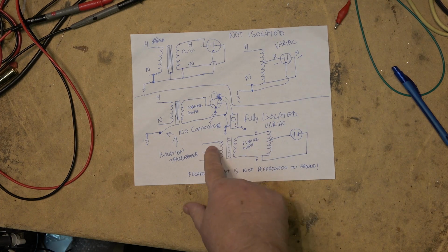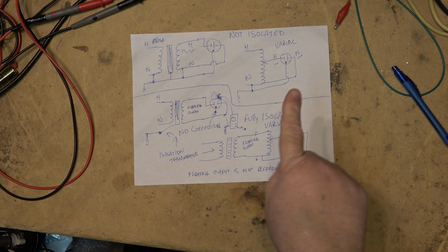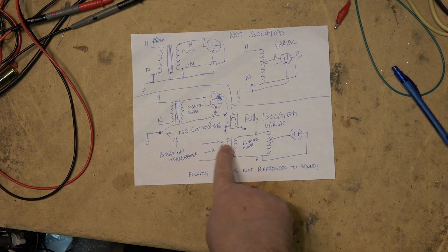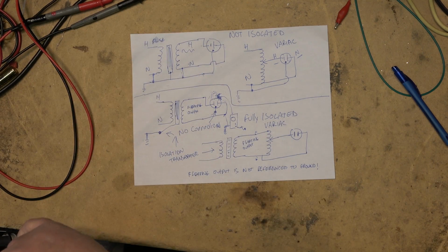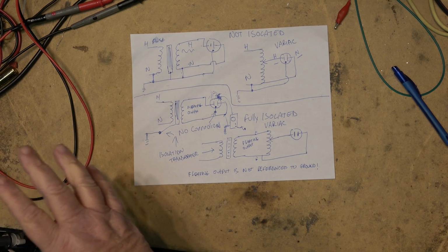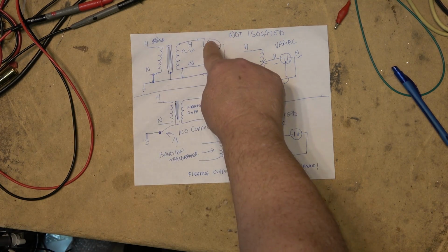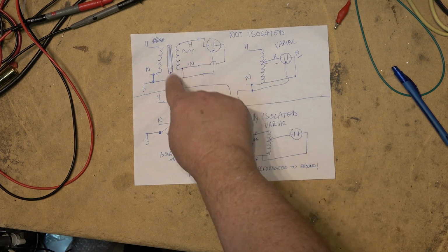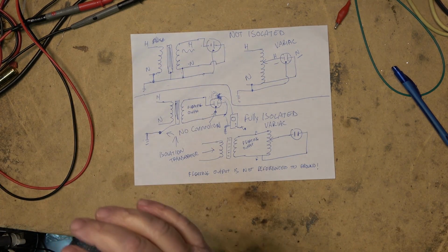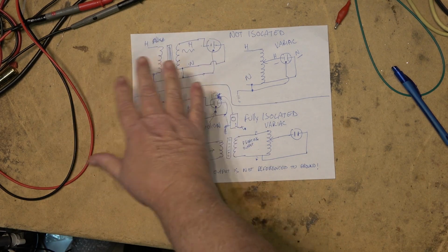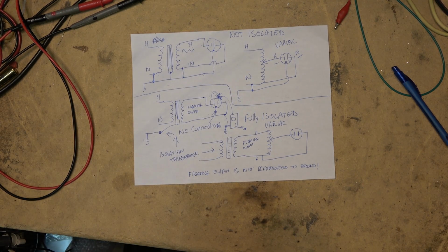You want an isolation transformer, or an isolation transformer going into a Variac, but it must be one that's fully isolated. And you can determine that with your meter. Your meter will tell you immediately. If you get any readings, either from the input side to the output side or the output side to ground, then you have an isolating transformer. Does that make sense? Isolating transformer and isolation transformer. I guess that's what we should call them.